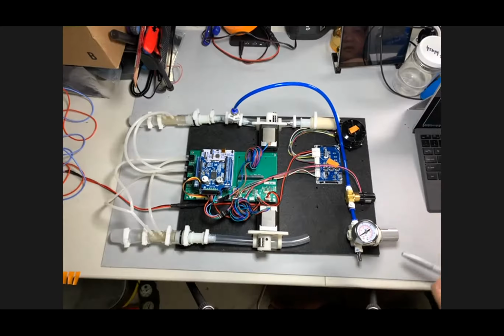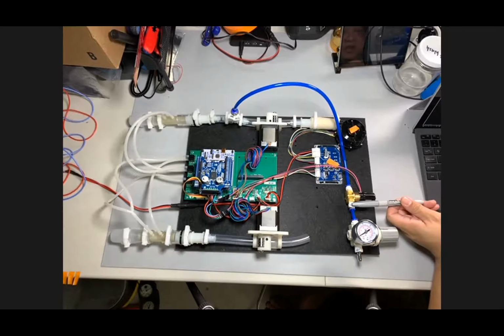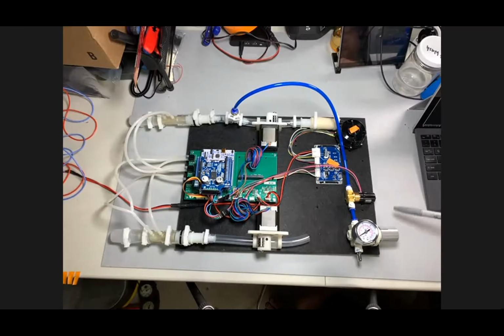Now this stuff here is pretty much prototype. I consider this part of the bench setup, the test setup, and the real ventilator starts here. So if we assume that the ventilator takes a 10 psi oxygen input, then we can start the ventilator right here. And we have been able to get the proportional solenoid demonstrated and working. We can do closed loop control on that. Whether this is the final solenoid, and the flow rates and things like that, are to be selected, and also what solenoids we can get in quantity, is up for grabs. But for the next 2 weeks, for the time being, we have a few of these and they are working. So I'm willing to call that locked for the purposes of the demo.